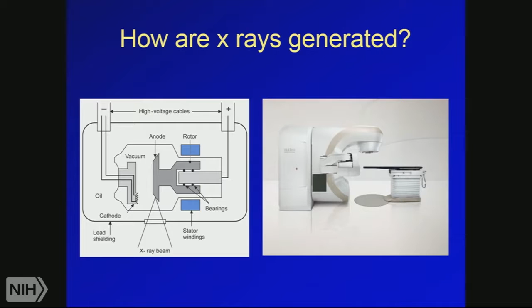The modern day radiation therapy machine is called a linear accelerator, which we abbreviate and call a LINAC. These machines can generate high energy photons as well as electrons. There is an electron gun inside of the treatment machine. The electrons are then accelerated in what we call the waveguide, which is seen right here. The electrons then get put through a bending magnet to have the energies come out this way. Those electrons strike a piece of metal. They then undergo what's called a Bremsstrahlung reaction and create photons. And those photons are then emitted through the head of the machine.